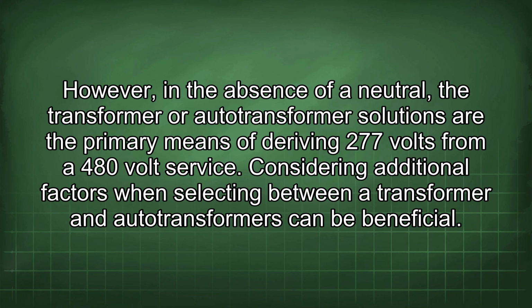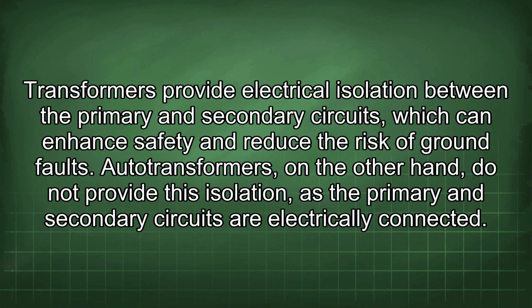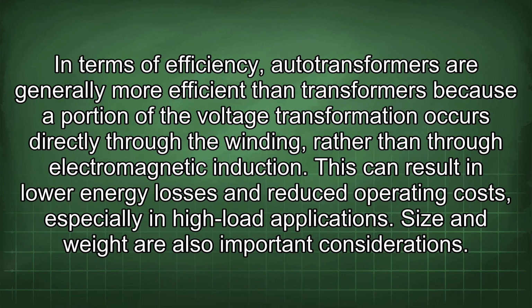Considering additional factors when selecting between a transformer and autotransformers can be beneficial. Transformers provide electrical isolation between the primary and secondary circuits, which can enhance safety and reduce the risk of ground faults. Autotransformers, on the other hand, do not provide this isolation as the primary and secondary circuits are electrically connected. In terms of efficiency, autotransformers are generally more efficient than transformers because a portion of the voltage transformation occurs directly through the winding, rather than through electromagnetic induction. This can result in lower energy losses and reduced operating costs, especially in high-load applications.